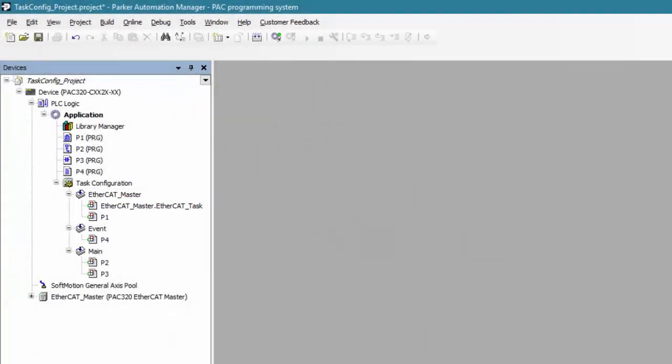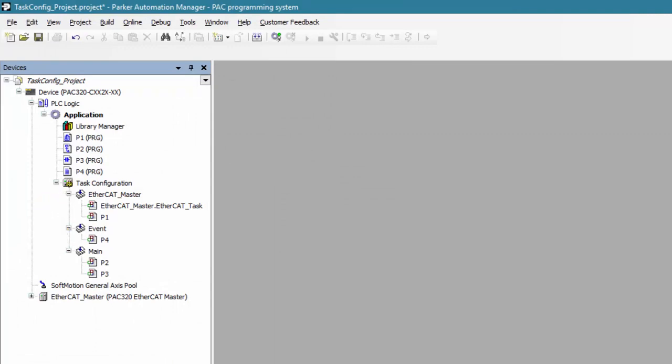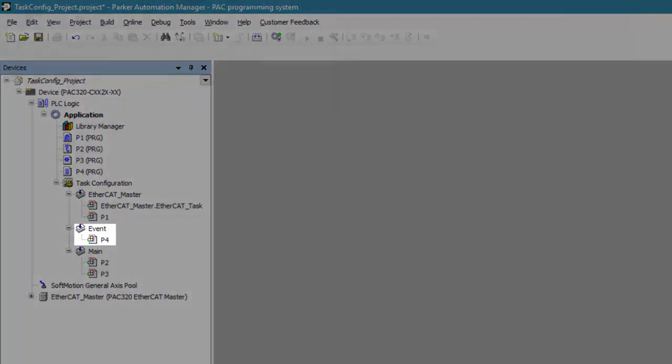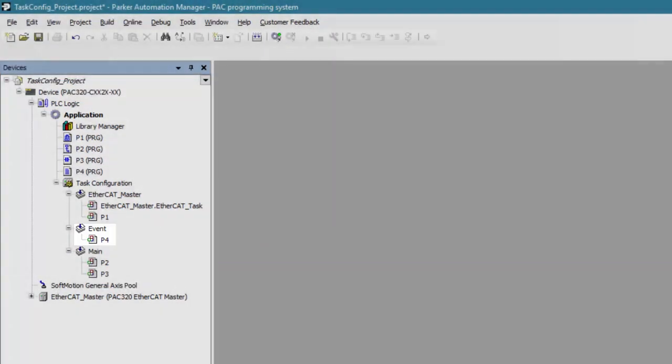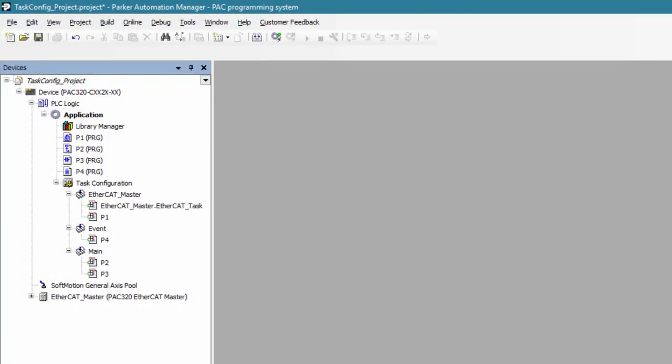However, the EtherCAT_task can interrupt both the event task and our main task. The event task is a single shot event triggered by a bool and only executes once. It can only interrupt the main task.